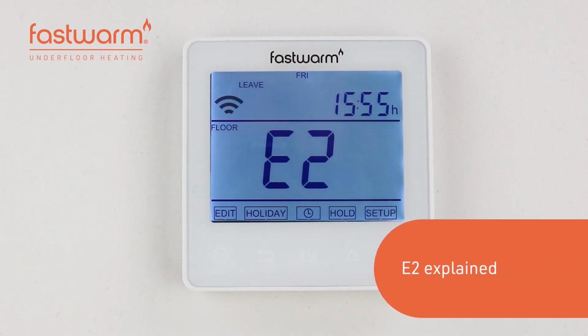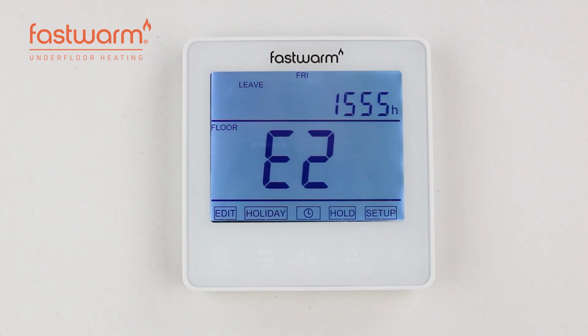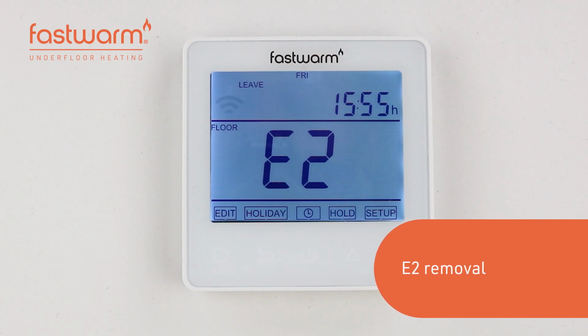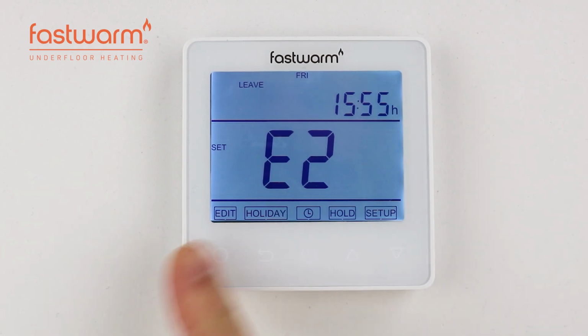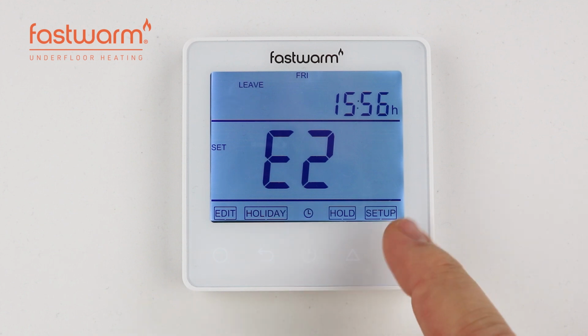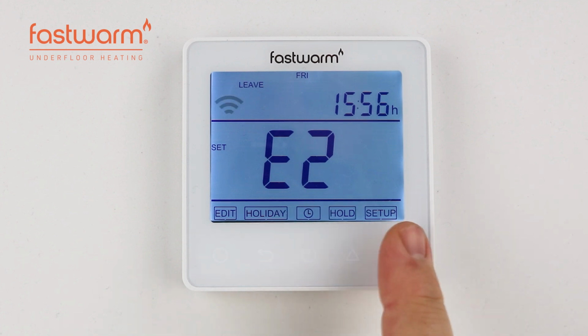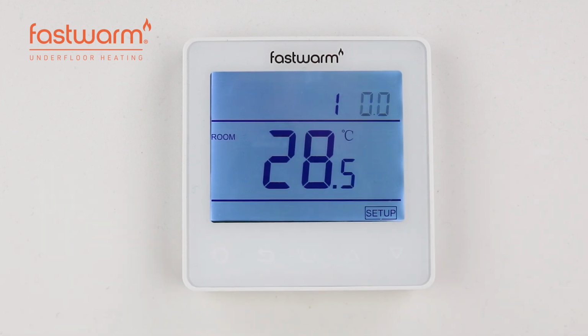E2 indicates that the floor sensor is not connected. To clear the E2 error, follow the next steps. Press the select button, then use the down arrow to choose Setup. Press the select button to confirm.